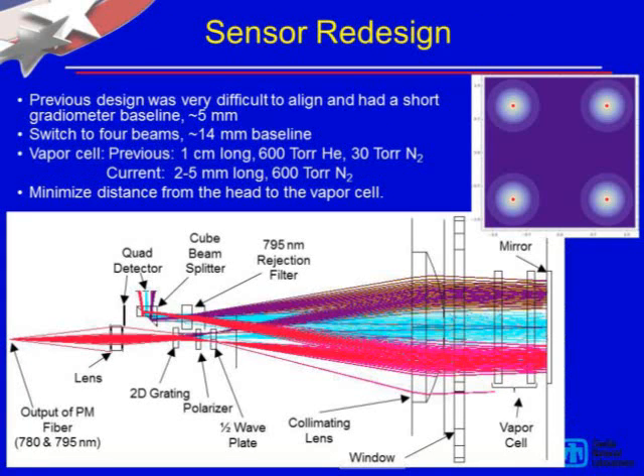Okay, so this is our sensor redesign. One of the critical things we wanted to address was the fact that the previous magnetometer had a separation between the individual sensors within the sensor head of only about 5 millimeters. We wanted to increase that to more than a centimeter, looking between 14 and 18 millimeters. Actually, I need to change the number on this slide—we ended up with a design that has about an 18 millimeter separation between the channels within the sensor.